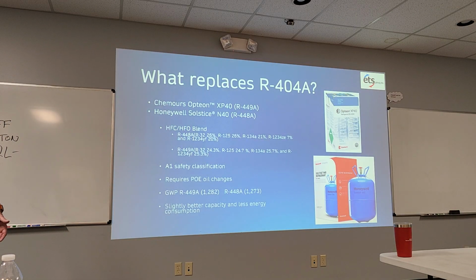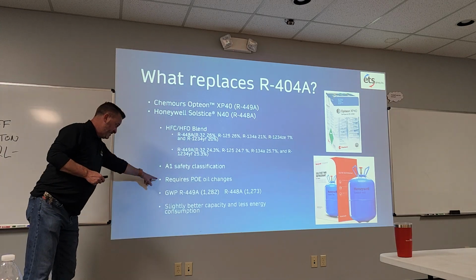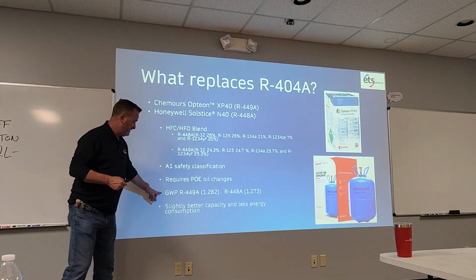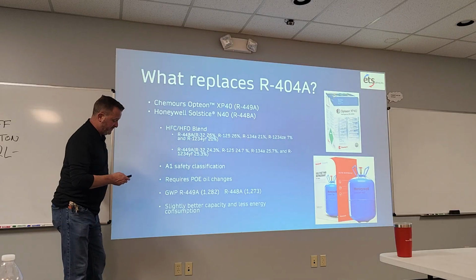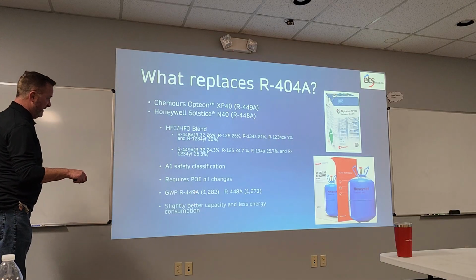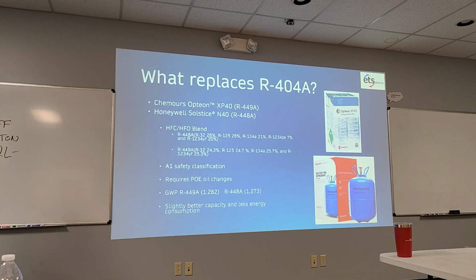So this is not an A2L, not considered mildly flammable like the other ones. It does require POE changes, oil changes. And the GWP is still better than obviously what 404 was, and that was the main thrust of this. You got 1282 and you got 1273 for the two. It has slightly better capacity, less energy consumption - that was the push towards that.